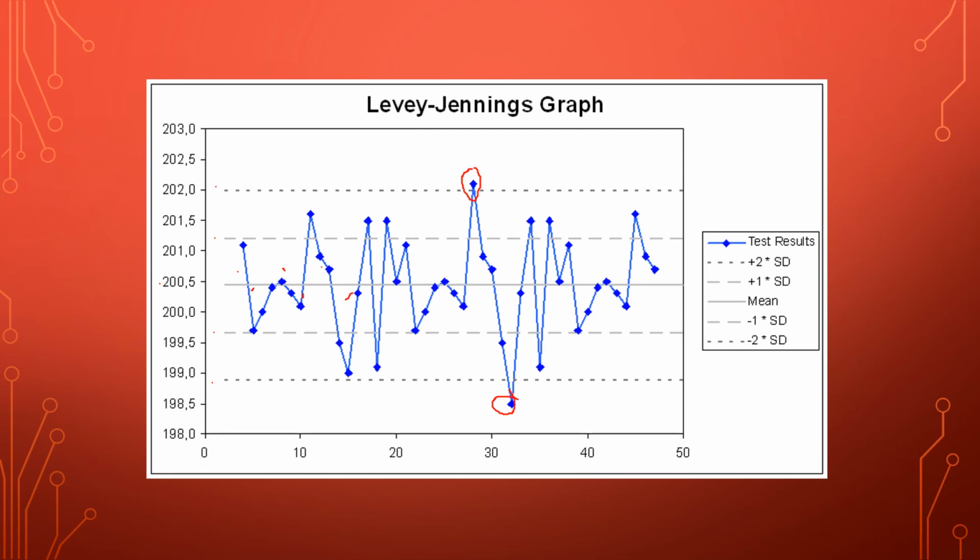An inspector who comes in will ask, okay, I want to see these results, these incidents that happened around the 30th day, looks like maybe the 28th and the 31st or 2nd day of your QC material, and I want to see what was done. Now, I'm saying days, but these could be runs. In some instruments, you'll run QC more than once a day. This could be morning, afternoon, evening, night, and you can go on and on.